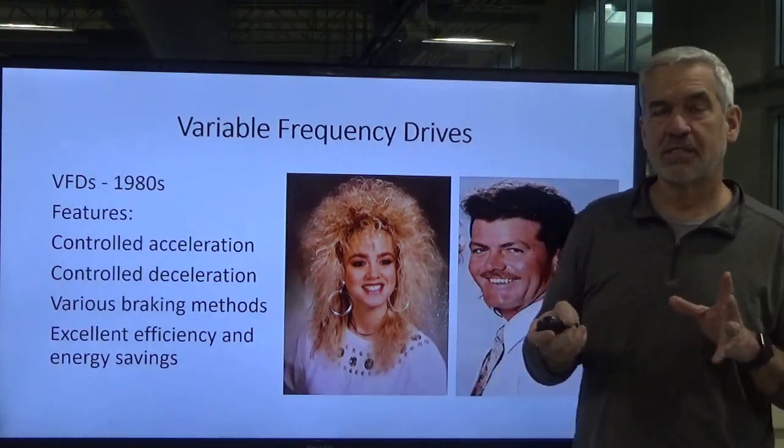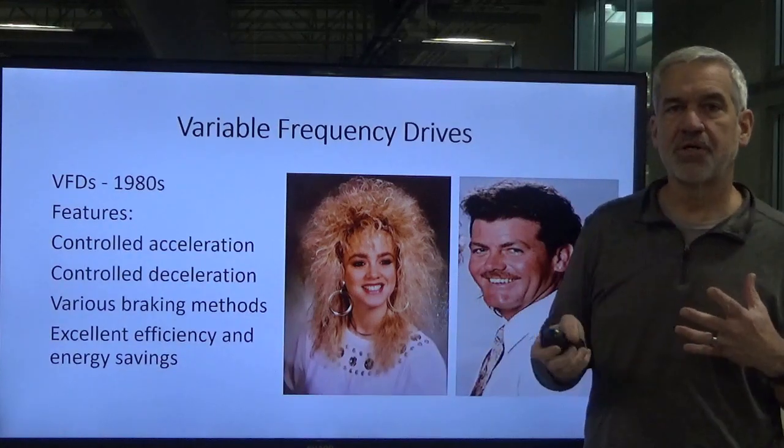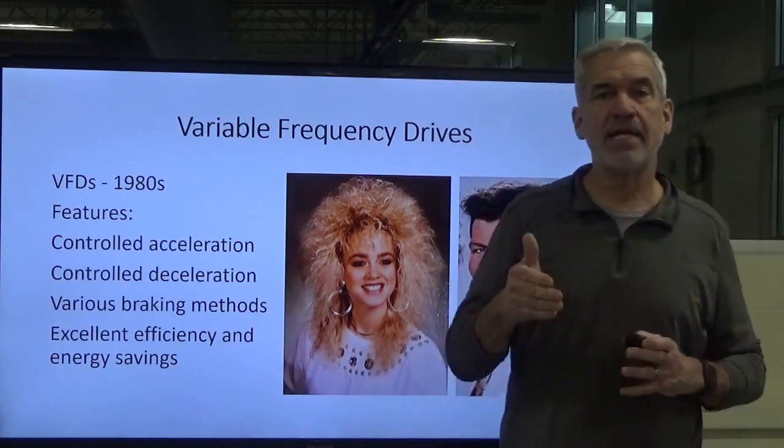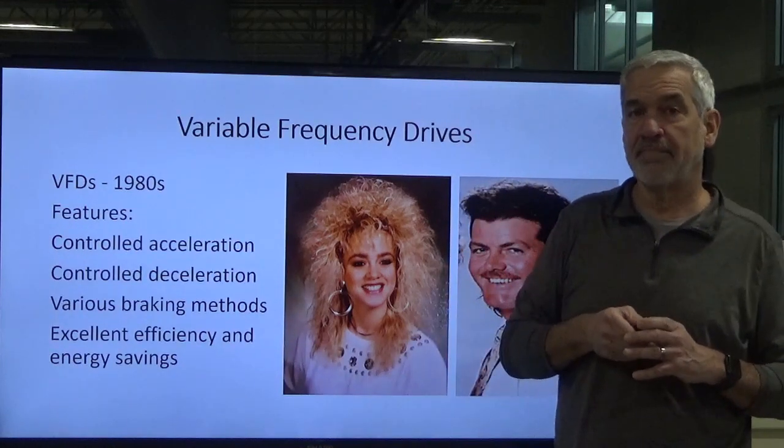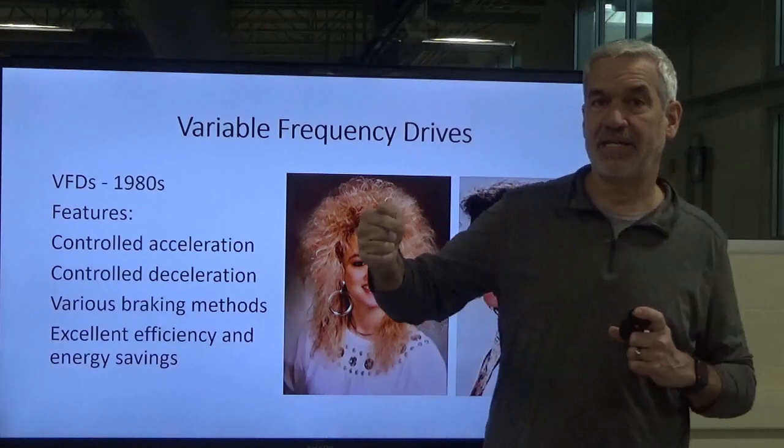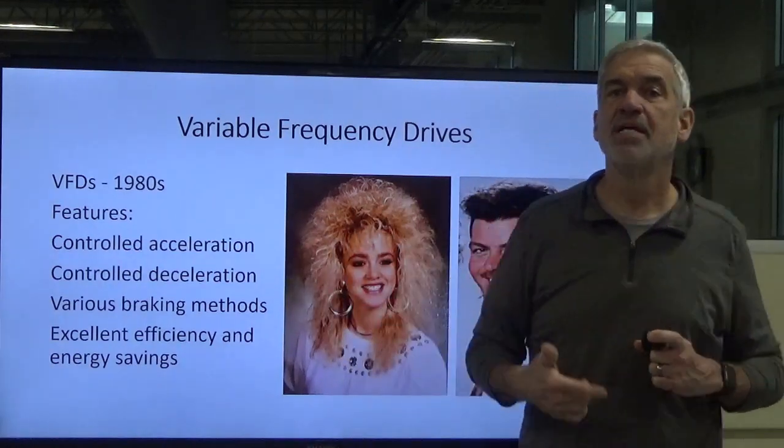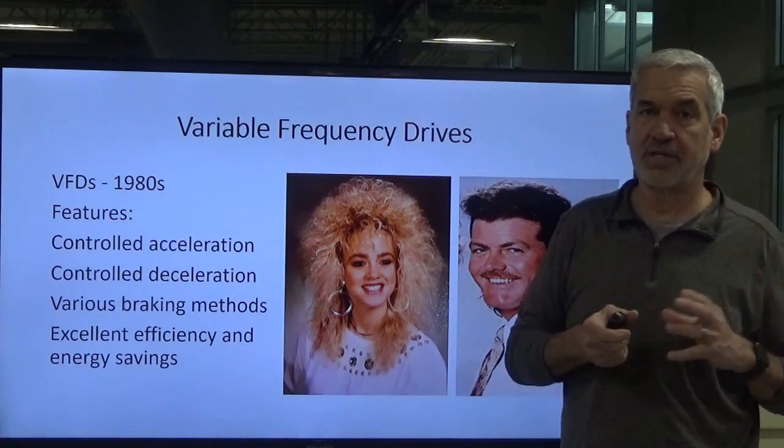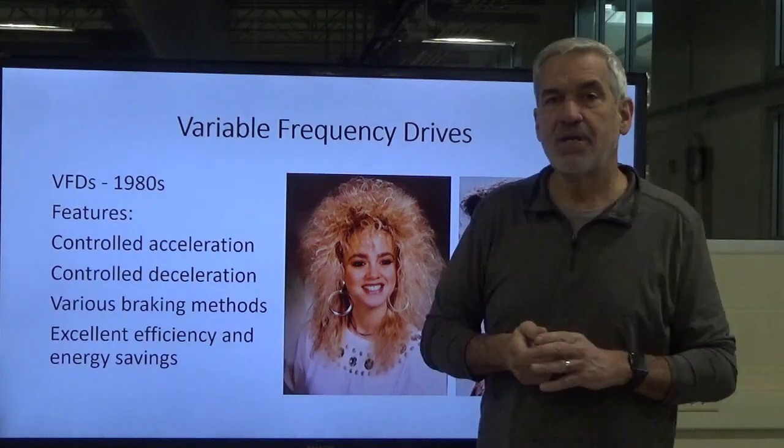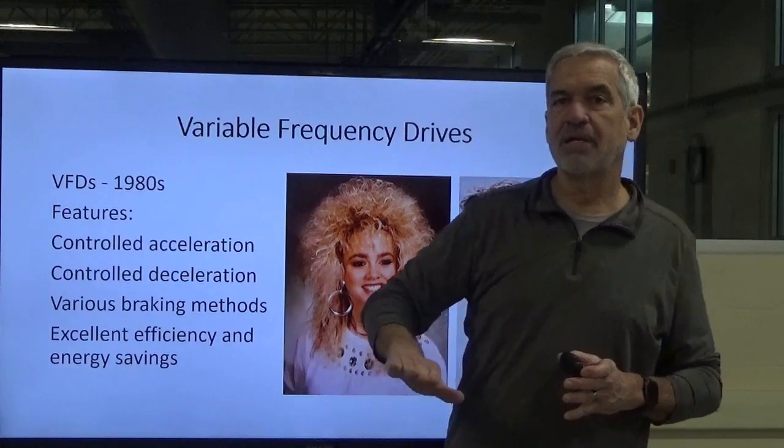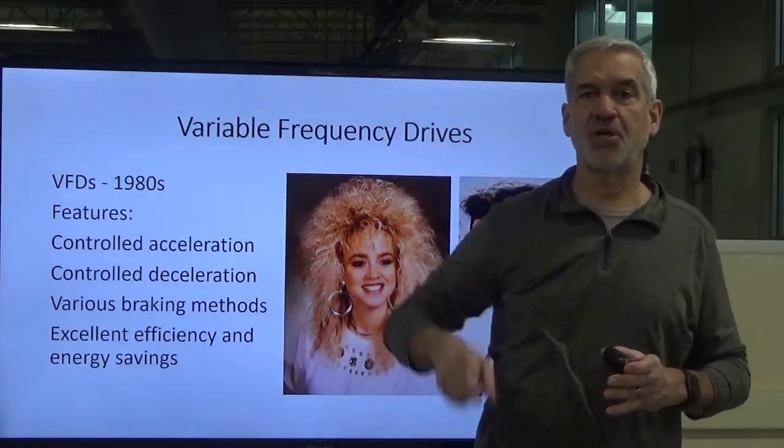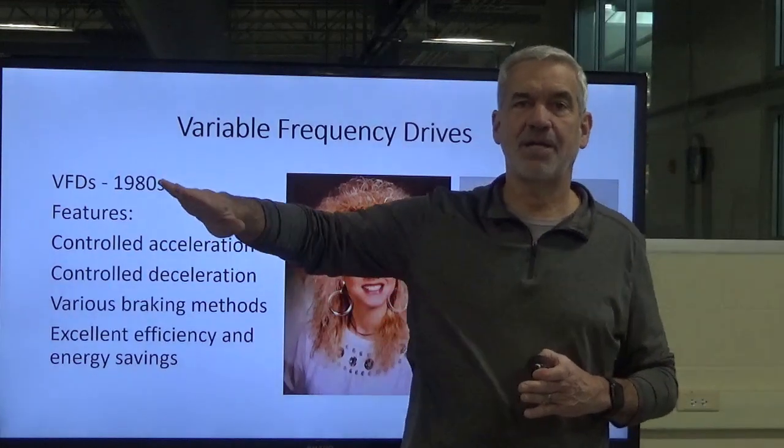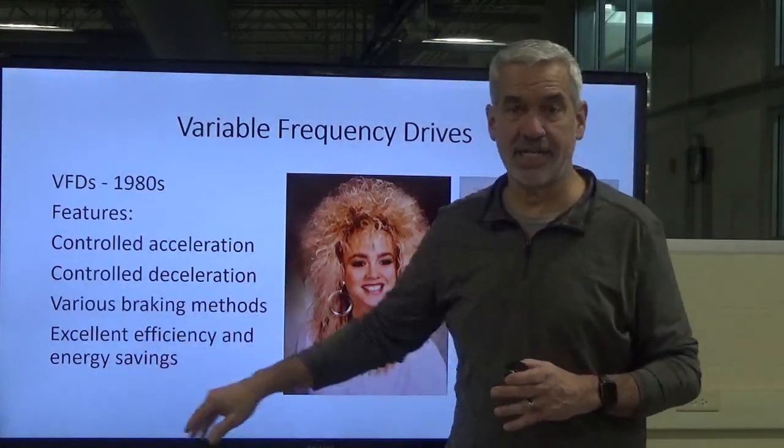It gave excellent efficiency and energy savings as well. Large motors will spike when they start up, and the utility company measures billing off these spikes. If you can bring that spike down and slowly bring the motor up, you don't get that big inrush current spike. Therefore it keeps it under the radar with the power company, and that's one of the ways it saves costs.